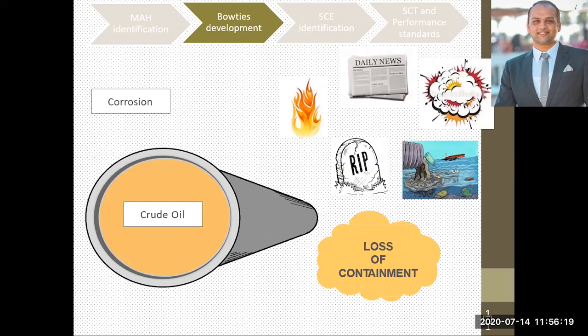Put as protection layers, they have figures which are called probability of failure on demand. And these are figures as well. They fail, for example, 1 every 10 times to be used, so we put 0.1. They will fail 1 every 100 times to be used, so we put 0.01. All of these numbers are put in certain equations, and it ends up with a number which can tell you what is the level of severity you have, or whether these safeguards are efficient and adequate and enough to protect you against what your company wants.